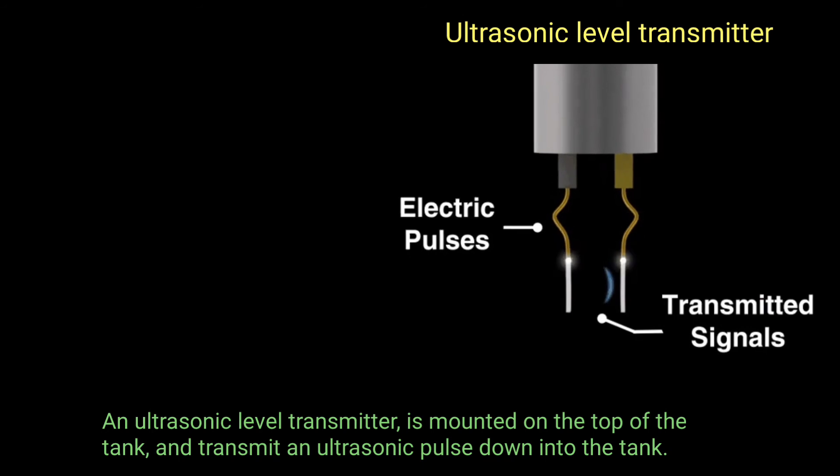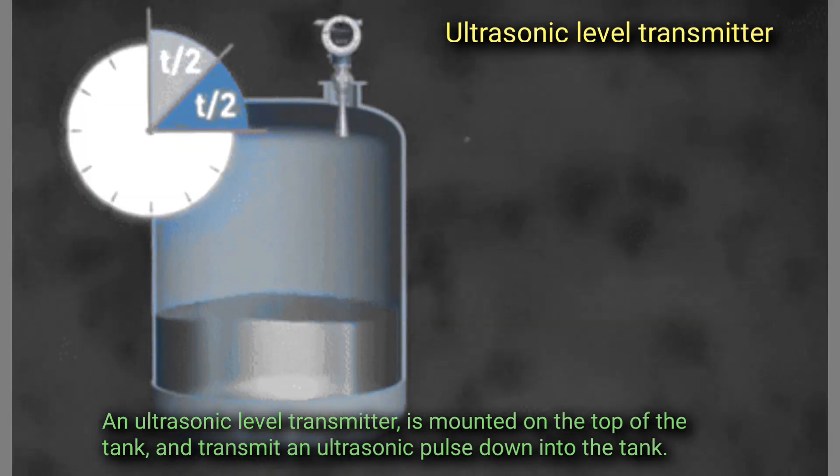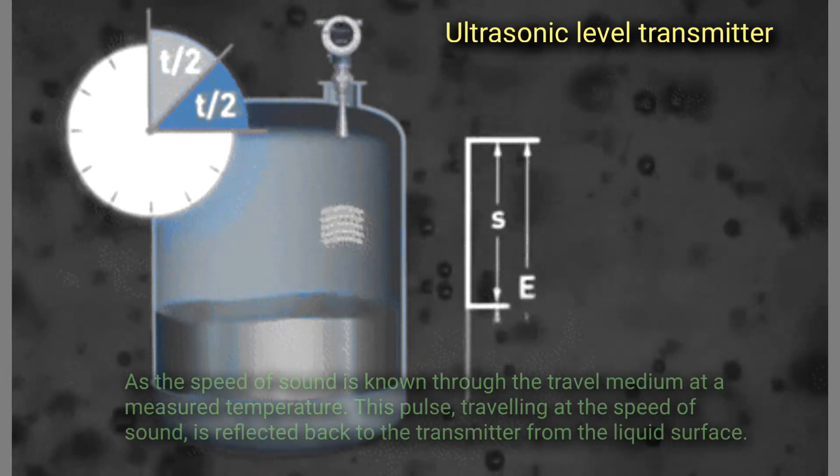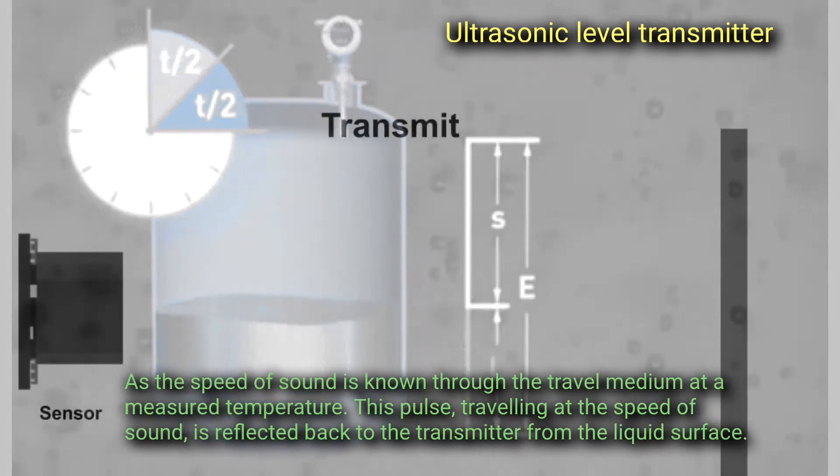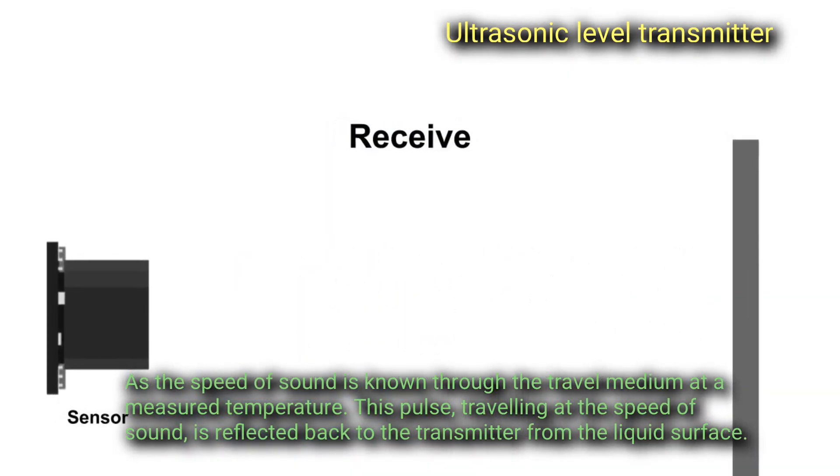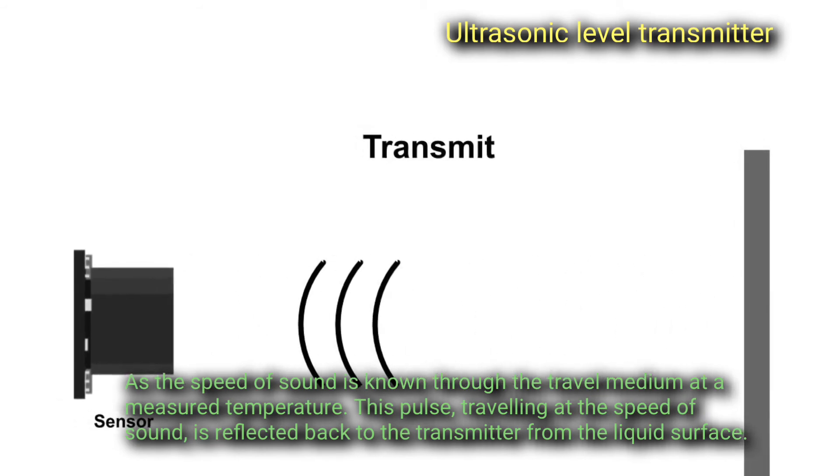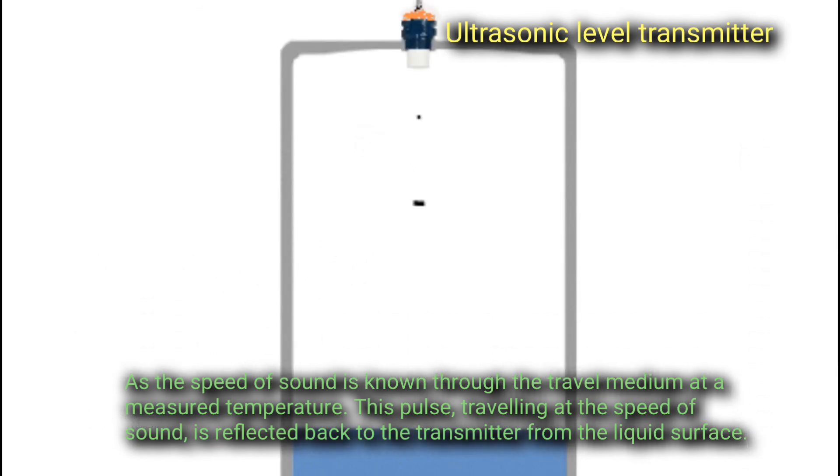An ultrasonic level transmitter is mounted on the top of the tank and transmits an ultrasonic pulse down into the tank. As the speed of sound is known through the travel medium at a measured temperature, this pulse traveling at the speed of sound is reflected back to the transmitter from the liquid surface.